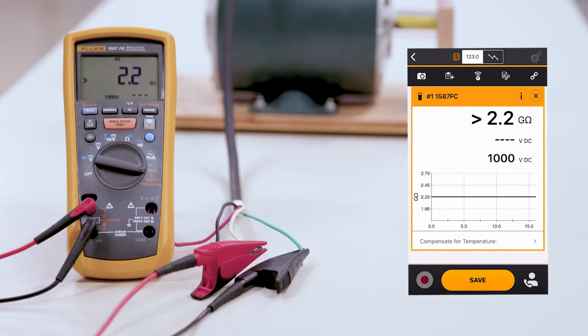Now you can see we've made all three measurements on the legs. We've validated that all measurements were greater than 2.2 gigaohms at 1000 volts DC. This is a good valid test for this motor. If we had seen a problem, we would have seen a lower breakdown in our ohms.